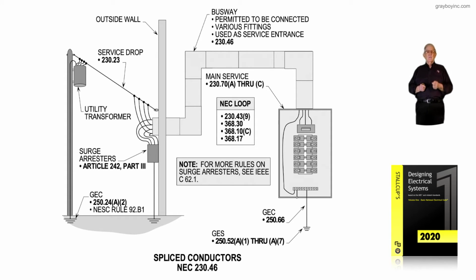So you can see the service drop is dropping down, and it is connecting in an approved manner to that busway. Also, a surge arrestor is set there in accordance with the new Article 242, Part 3, I believe it is, that deals with surge arresters. It's connected to ground to divert surges coming down the line and to regulate the voltage coming in and terminating to the main and the service equipment. But notice that busway is being spliced together.